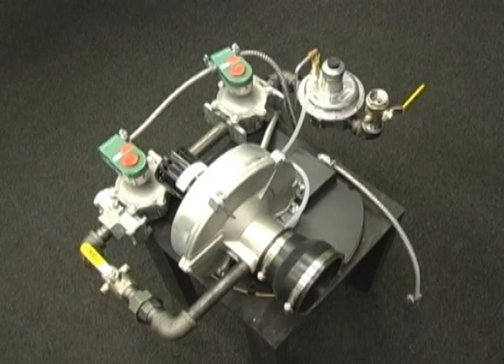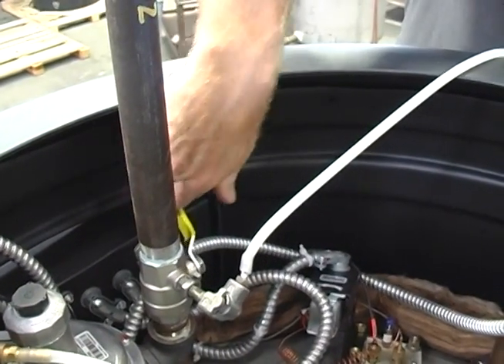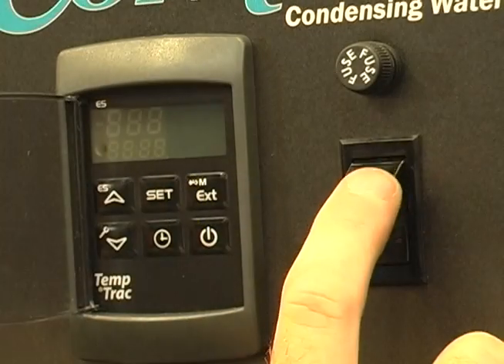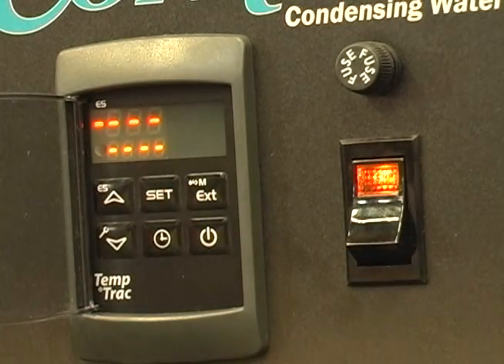For water heaters 500,000 BTU input and higher with a modulating burner, combustion must be optimized during startup at both low and high fire. Doing this requires that the Temp Trac operating control be placed in manual modulation mode. To begin, open the main gas valve and move the rocker power switch to the on position.